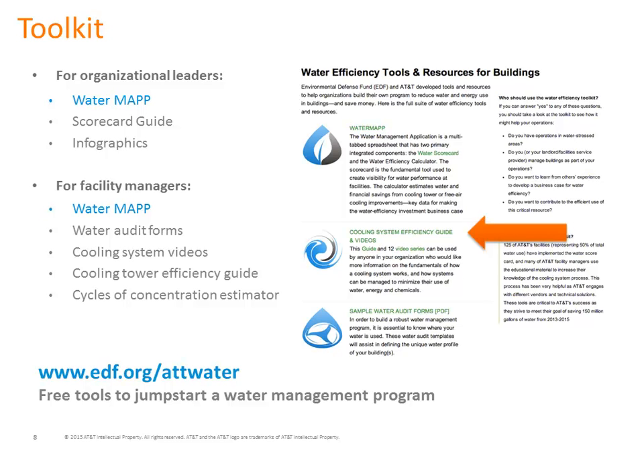For those who have looked into this, water quality varies throughout the United States, and it's unlikely any two facilities will have exactly the same water quality available for their cooling tower. So cycles of concentration will vary from one location to another. What we've done is put together a tool that allows you to input the water quality characteristics for your facility, and it automatically calculates a recommended maximum permissible cycle of concentration using a traditional chemical treatment program. You can then compare this to your current operating conditions to determine if you have an opportunity for water savings. It's a nice, handy tool.